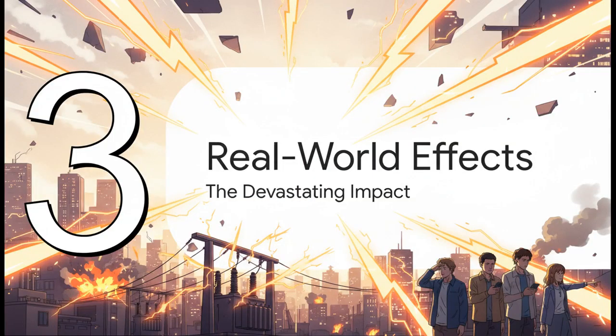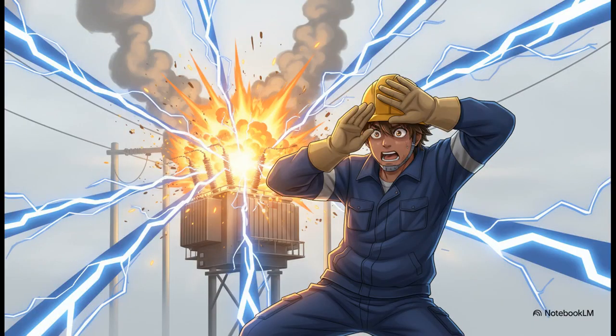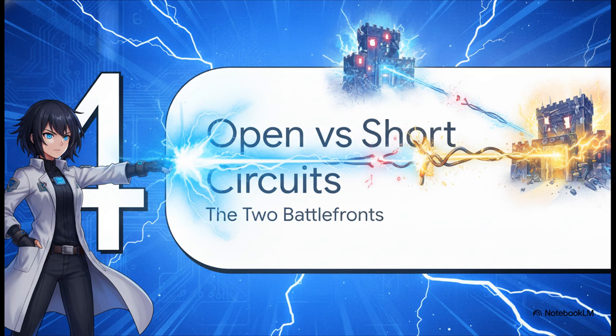Moving to Section 3, the shocking real-world effects, the devastating impact. So what physically happens to the real world when all that current escapes? Well, it is truly terrifying. You get this massive overcurrent flow because the electricity finds a new, ridiculously easy path, drawing a huge amount of power. This instantly creates a deadly shock danger for anyone nearby. We're talking total loss and literal burning of equipment, severe disturbances ripping through the interconnected circuits, and, as we saw earlier, devastating electrical fires. The sparks actually ionize the surrounding air, which leads to those massive violent explosions you see in transformers.